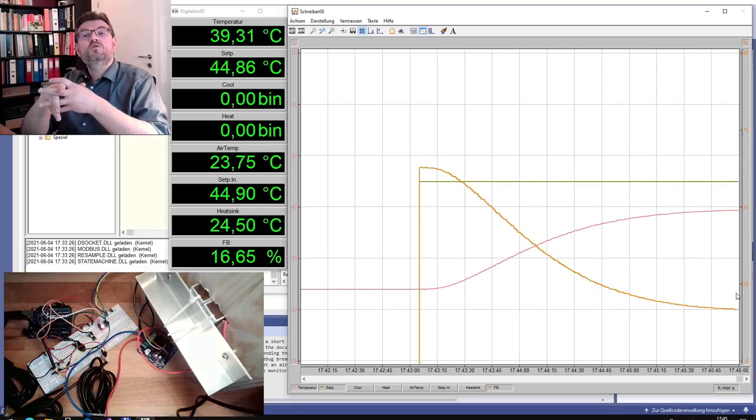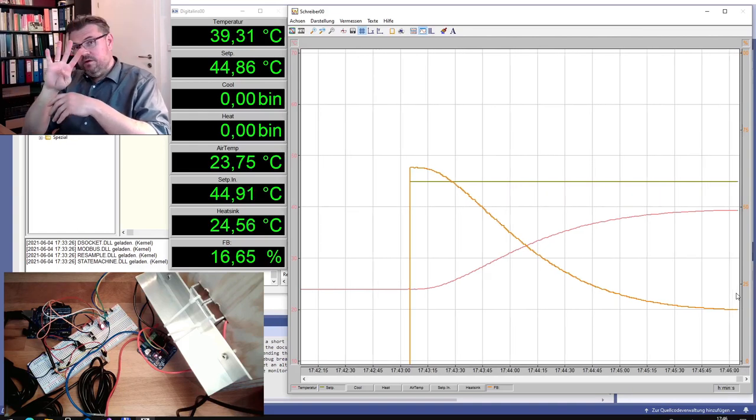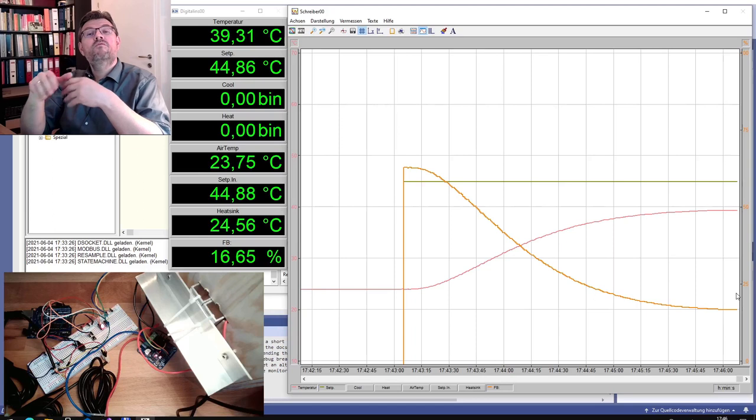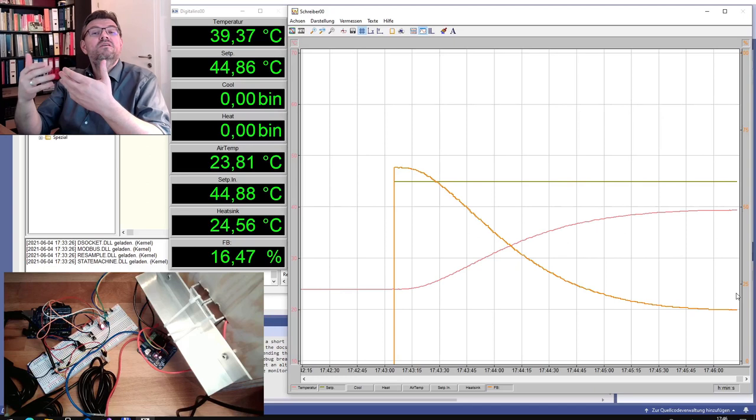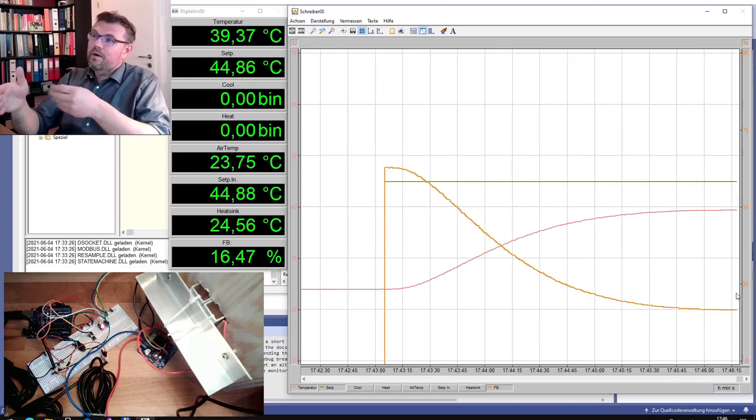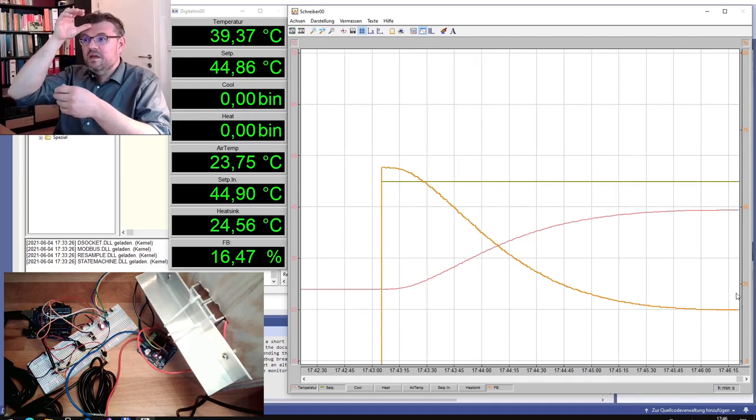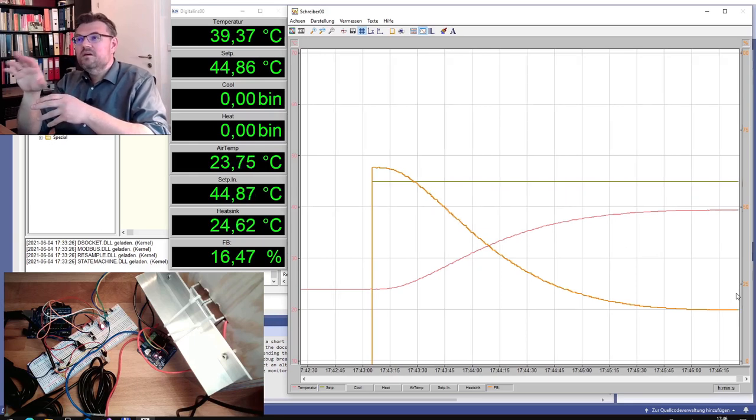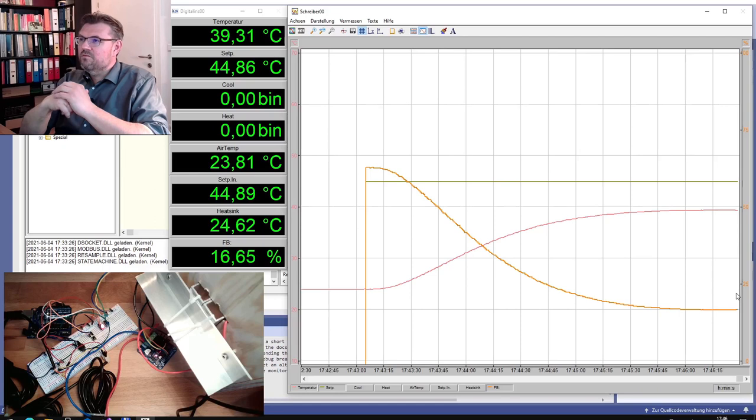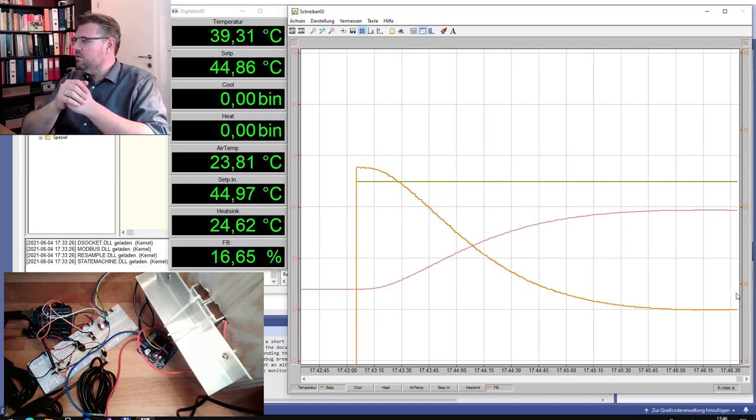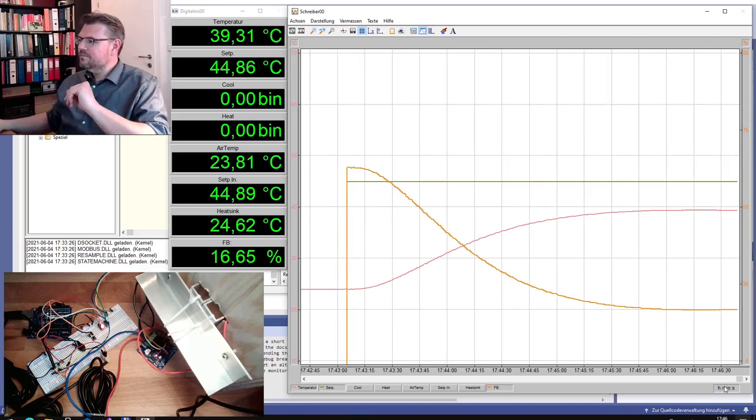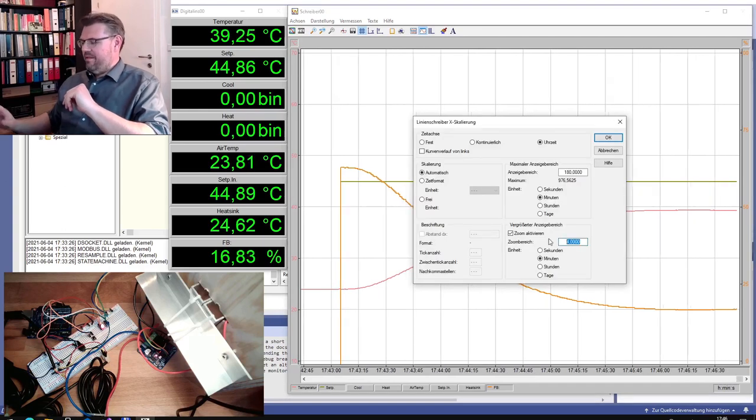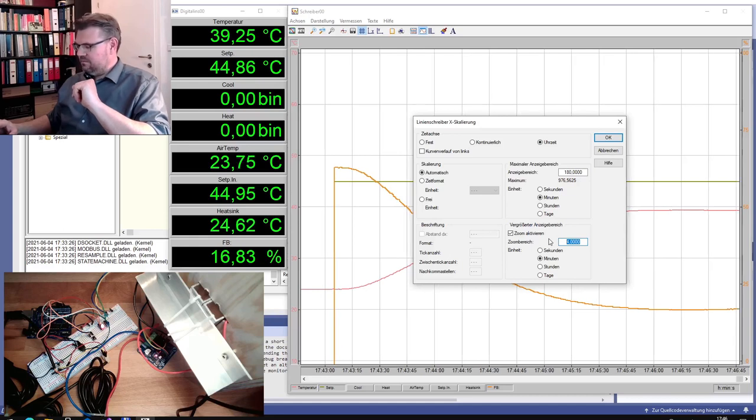By the way, the proportional gain factor is currently set to 3. You see right now we have around 40 degrees. We want to have 45, so the difference is 5 degrees. 5 multiplied by 3 is around 15, and the value is 16.4. Well, we have a little bit above 5 degrees. So this is how this is built. The control difference is currently 5.5 degrees, so it's 16.5 for the correcting variable.